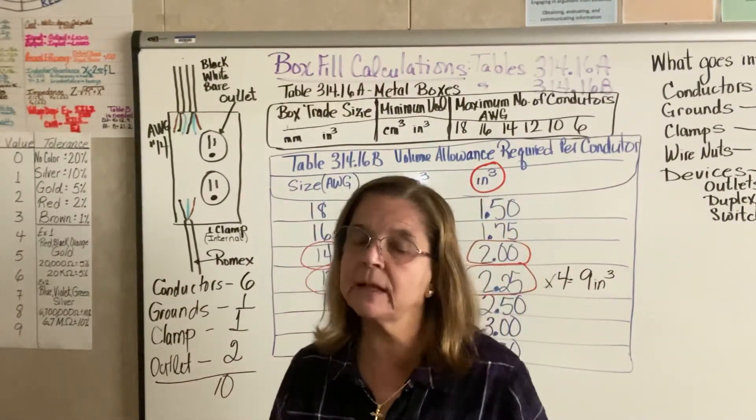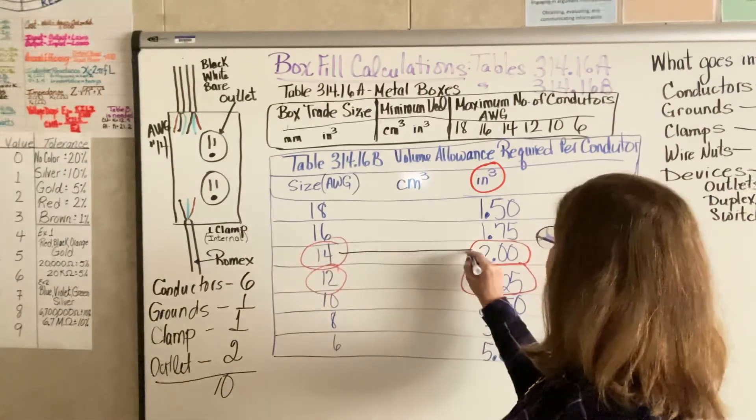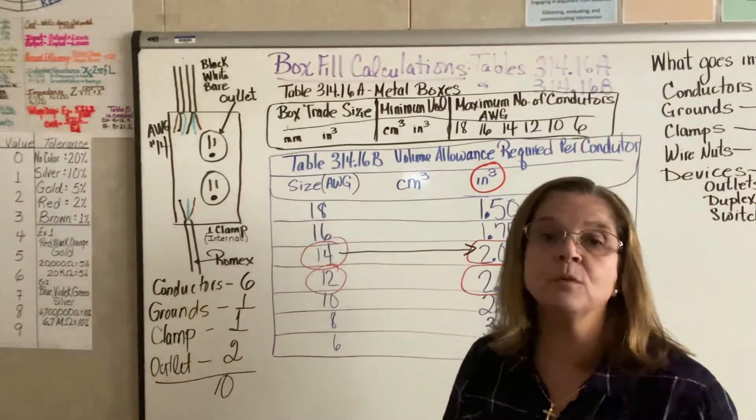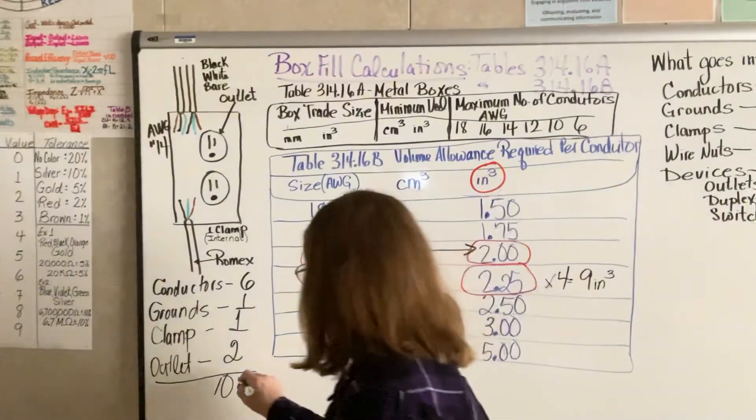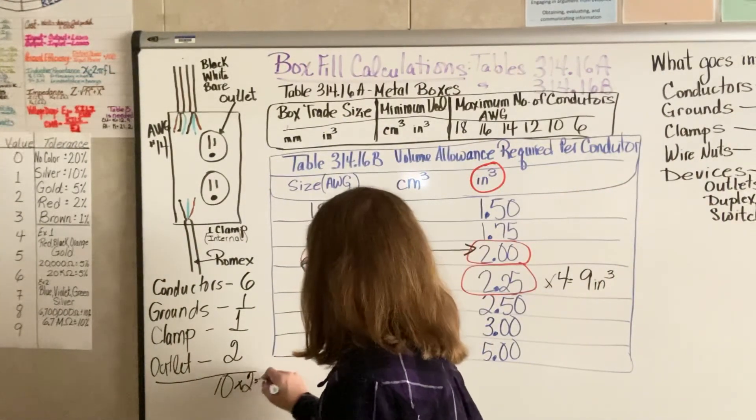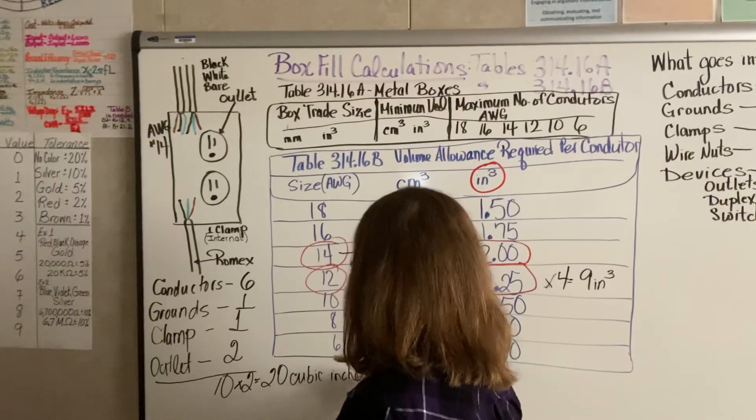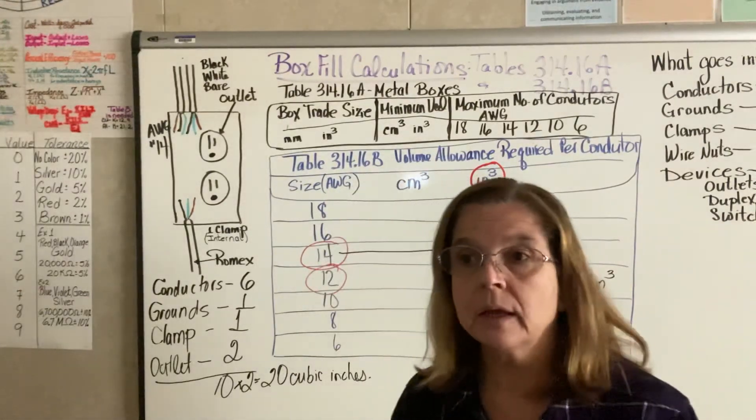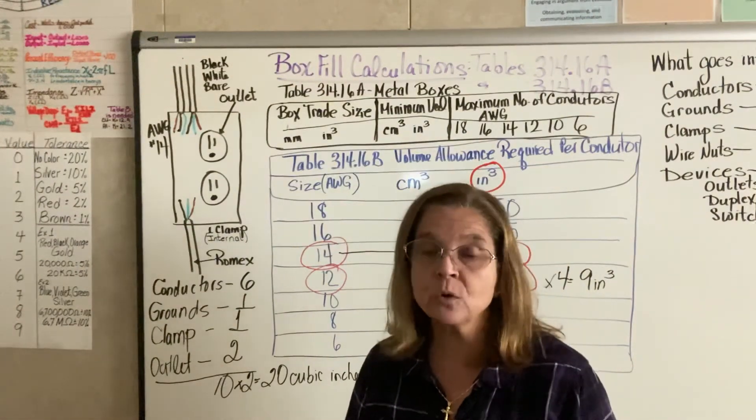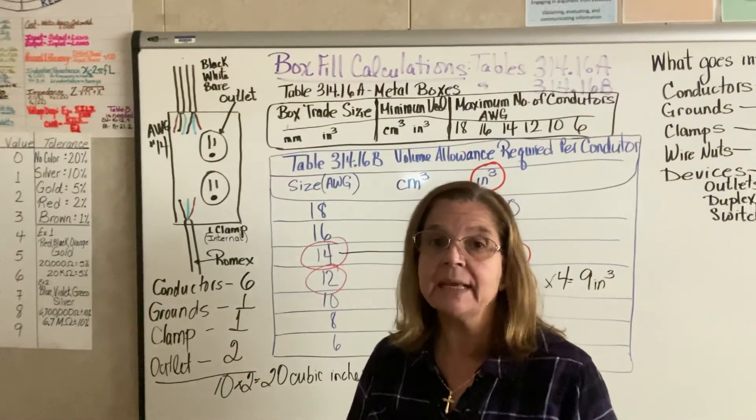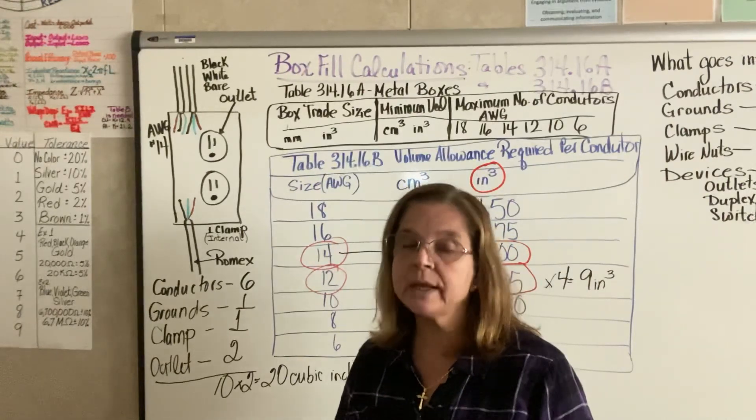Now, I still haven't figured out the volume. I go to table 314B, go to number 14 and I'm looking at the cubic inches. And over here the cubic inches says 2 cubic inches per conductor. So I do 10 times 2 and I have 20 cubic inches. So when I choose my non-metallic box I need to choose one that has more space than 20 cubic inches. If I pick 20 it's too tight.